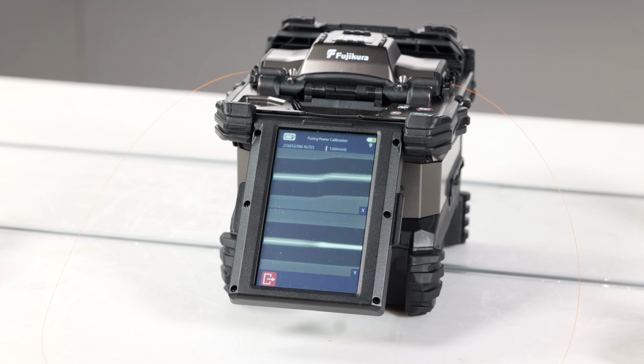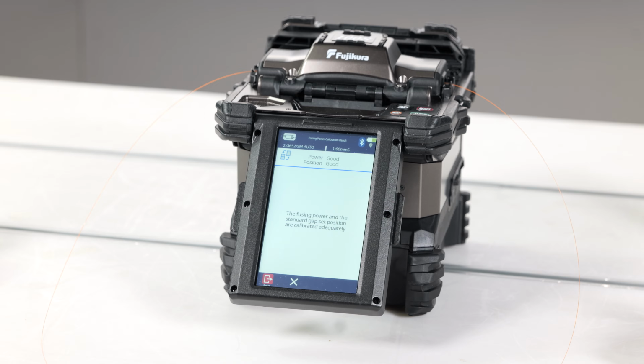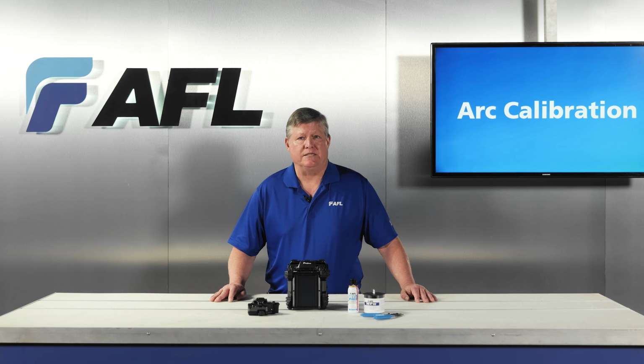It's important to understand that automatic splice modes are not a substitute for arc calibration. Auto modes make small adjustments between splices, but they rely on a properly calibrated starting point. The best practice is simple: calibrate first, then splice. This sets the foundation for consistent results throughout the day. Once arc calibration is complete, the splicer Ready screen is displayed. The splicer is properly prepared for the next step in the workflow.